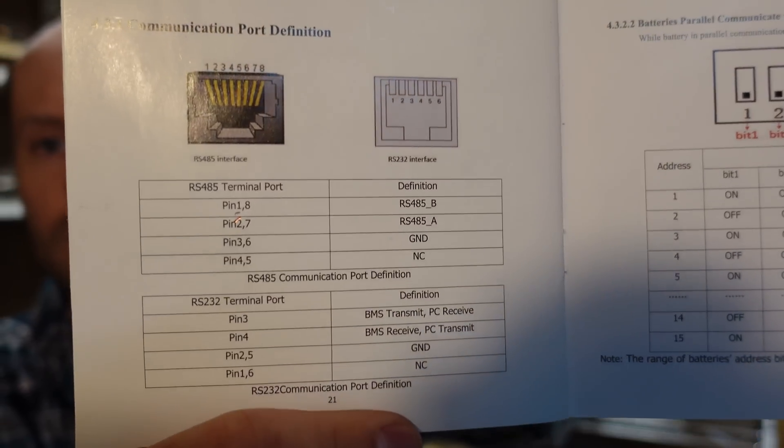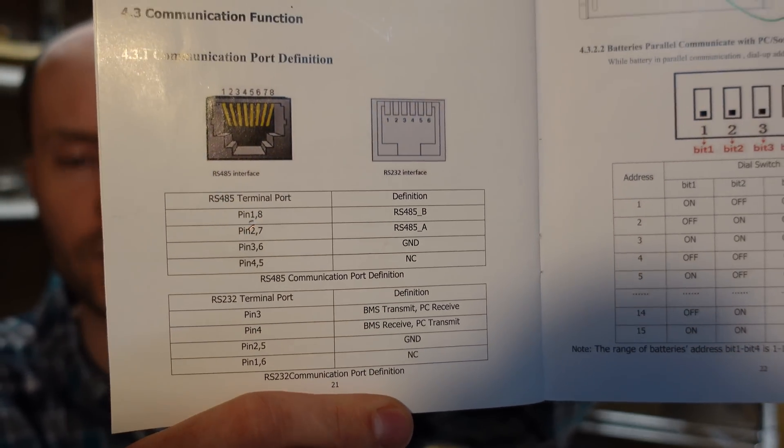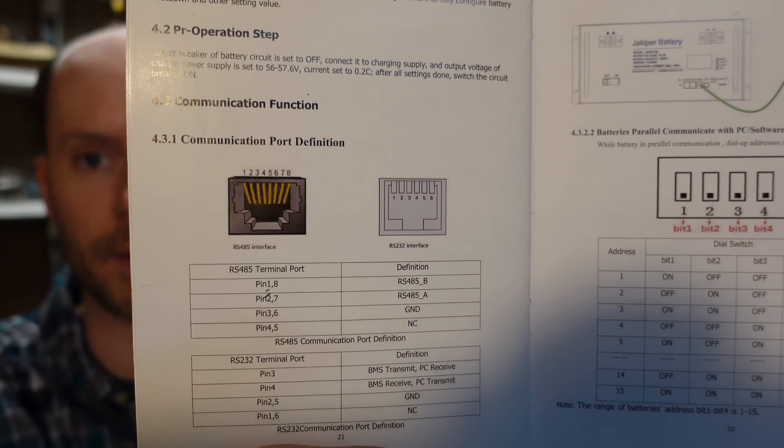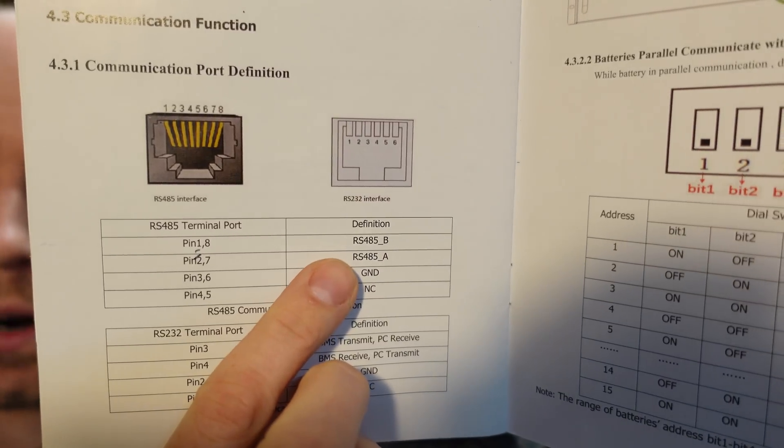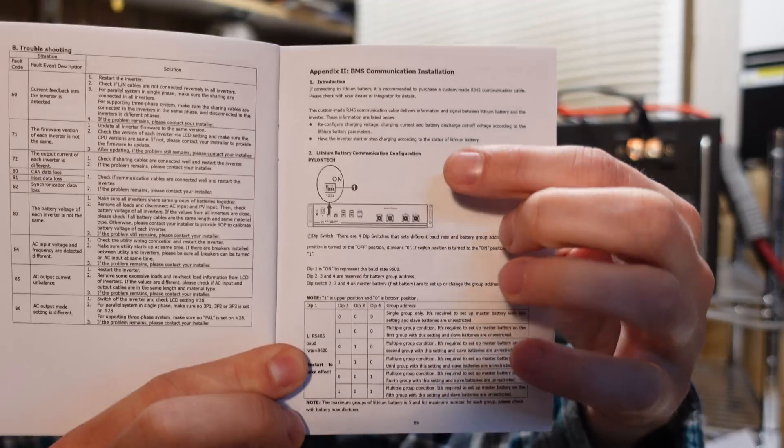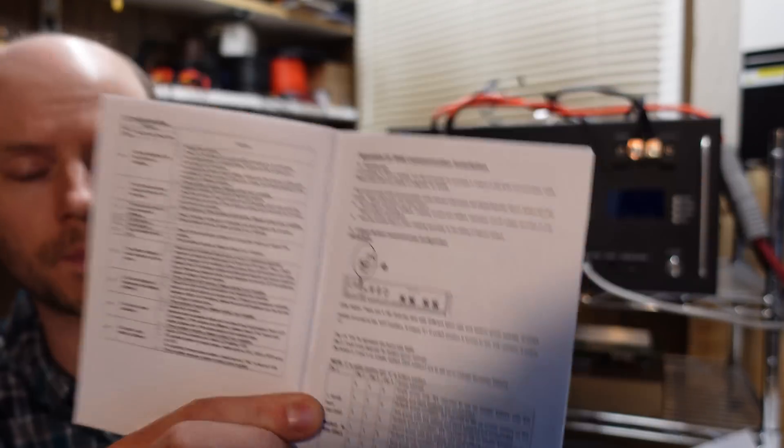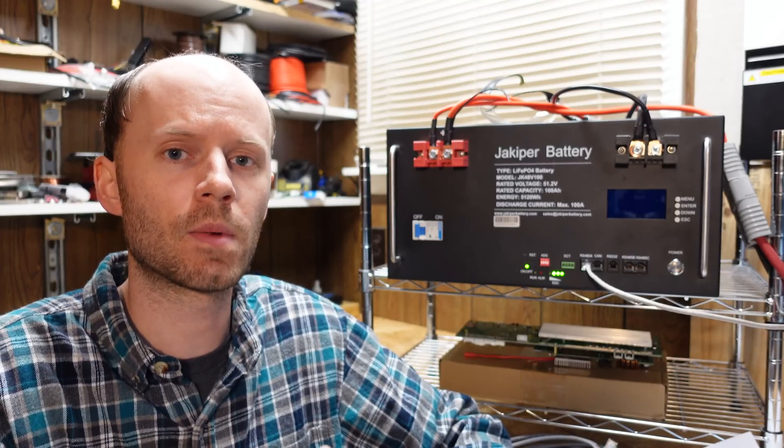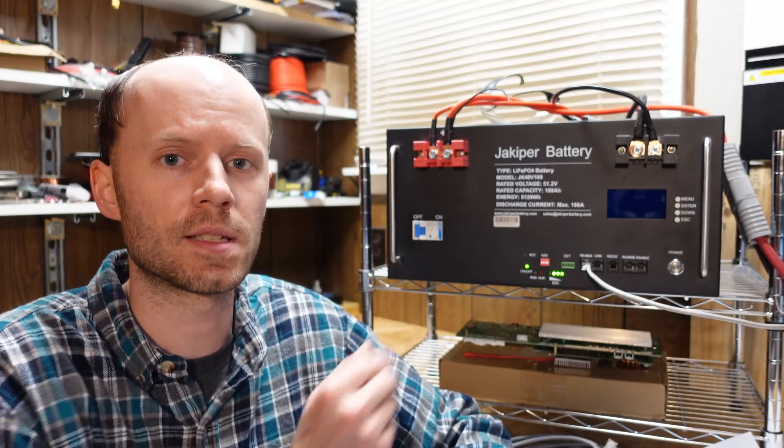So the Jakiper user's manual provides pinout information on the RS-485 port of this battery. So we can see which pins we need for RS-485 A and B. Now the manual for the MPP solar inverter does not make any mention of the pin assignments on the BMS connector. Their user's manual has an appendix for this. However, it's very specific to certain brand and model of battery, which I assume are the ones MPP solar has actually tested with their inverter.